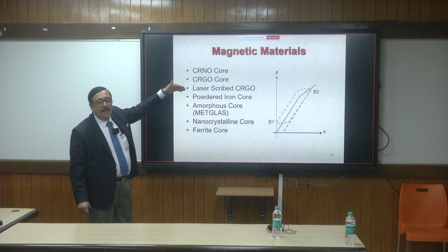So now you will be able to understand, when you go up to higher frequencies, ferrite cores, even though they are only roughly about 0.4 Weber per meter square, can handle several kilohertz easily, the normal ferrites. And you get the special grade of ferrites that can operate beyond 200 kilohertz. So ferrites are the choice for the high frequency, and for the low frequency you can use any one of these. And this is for DC chokes in high frequency applications, and this is mostly used for AC chokes in line side chokes of converters. Nanocrystalline cores, I am told there are some manufacturers in this country yet, but I'm not sure. This is made by Usha Amorphous in Delhi.